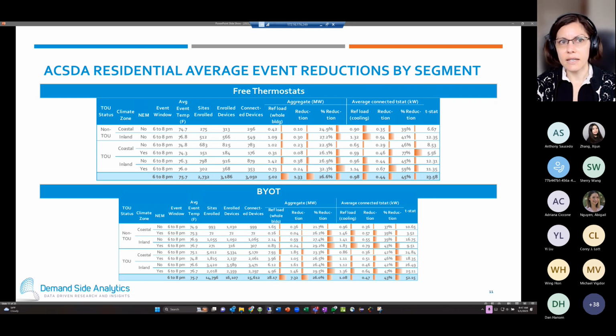We've noticed that understanding not only what the overall average reductions are, but the reductions per connected thermostat, is important, as the population of connected thermostats changes over time. If you have a substantial portion that are disconnected, those thermostats dilute your reductions, because thermostats that are not connected do not receive signals or produce reductions.